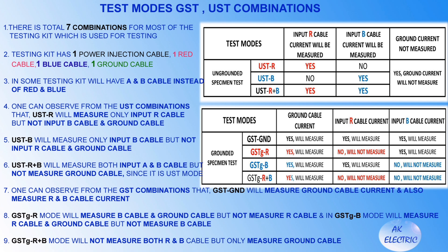UST B will measure only the input blue cable but not the input red cable and ground cable. UST R plus B will measure both input A and B cables but not the ground cable, since it is in UST mode. From the GST combination, GST Ground will measure ground cable current and also measure red and blue cable current. GST R mode will measure blue cable and ground cable but not red cable. In GST GB mode, it will measure red cable and ground cable but not blue cable.